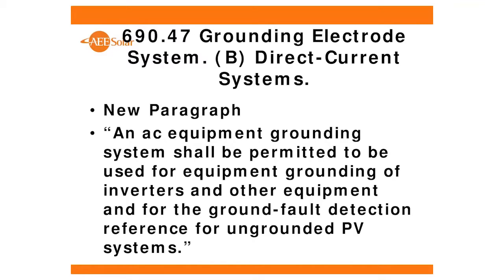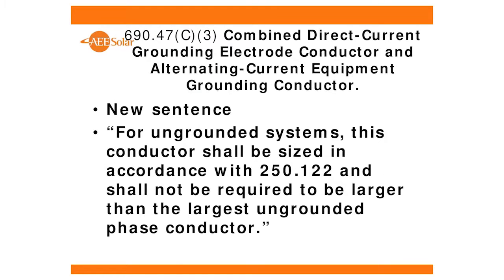Okay, let's see. I think the AC equipment grounding conductor should be permitted to be the ground fault reference. That's in the 2014 code. Again, we simplified it further in the 2017 code. And also a new sentence in the 2014 code for ungrounded systems: this conductor shall be sized in accordance with 250.122, not 250.166, and shall not be required to be larger than the largest phase conductor. So for an ungrounded system, what that's saying is that your AC equipment grounding conductor can be used as your conductor for ground fault detection and all that, and you don't have to have a grounding electrode conductor in that.